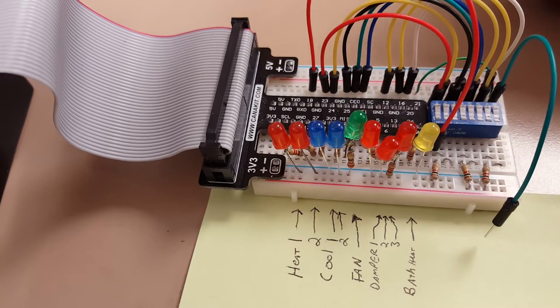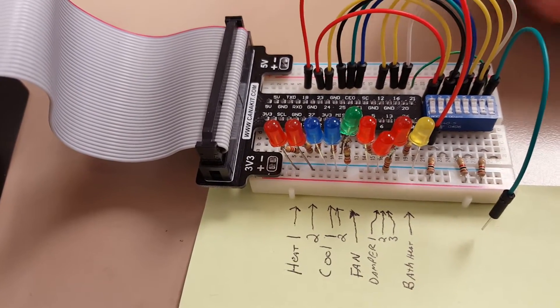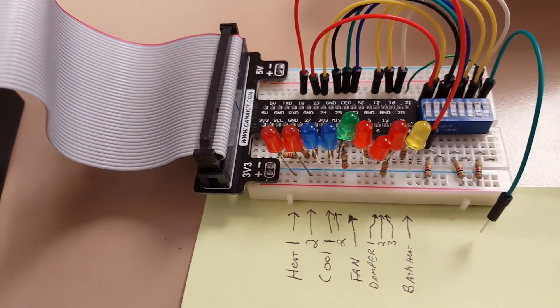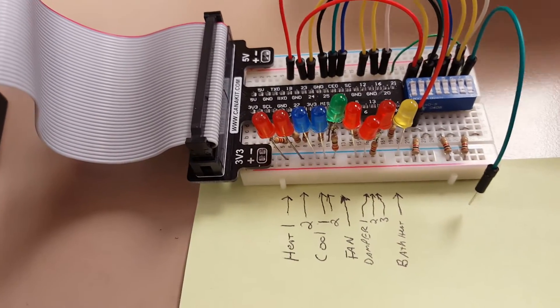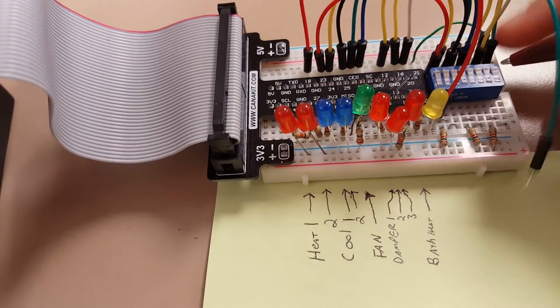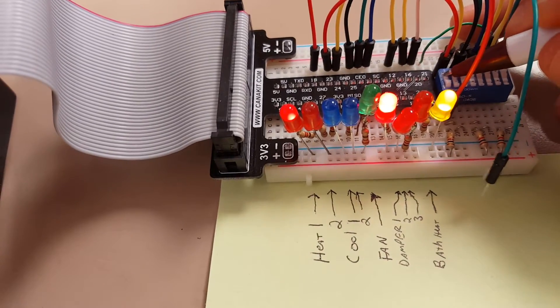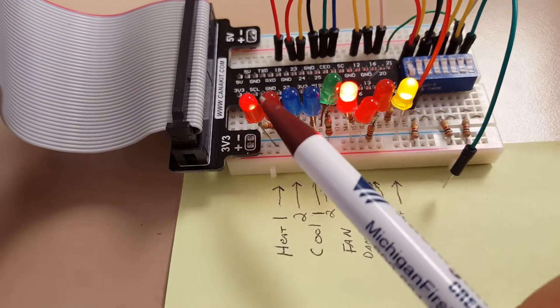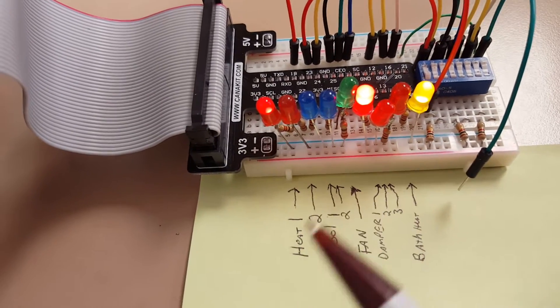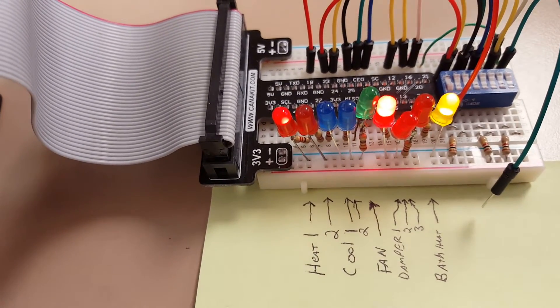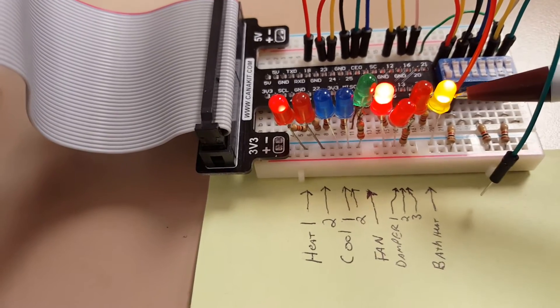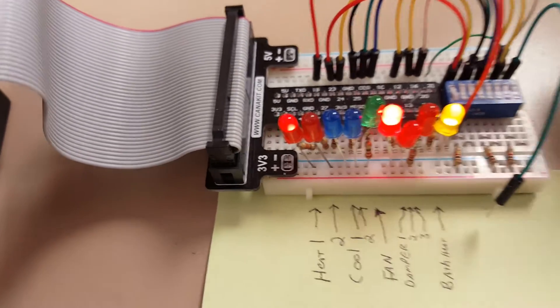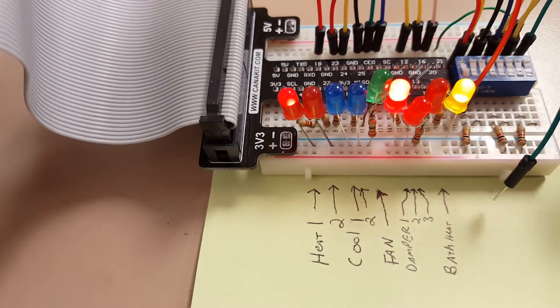So the first thing you're going to see is that indeed one stage works. This is our call for heat to the furnace that's going to turn on the furnace. This opens the damper to that zone, and this is actually an auxiliary bathroom enable point for my friend who has some auxiliary heat in the bathroom. He doesn't want that enabled unless there's been a call for heating within the last 24 hours or so.